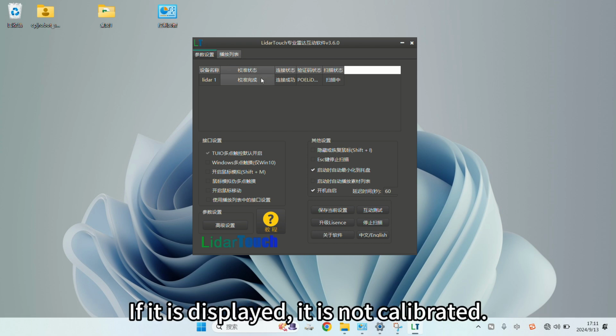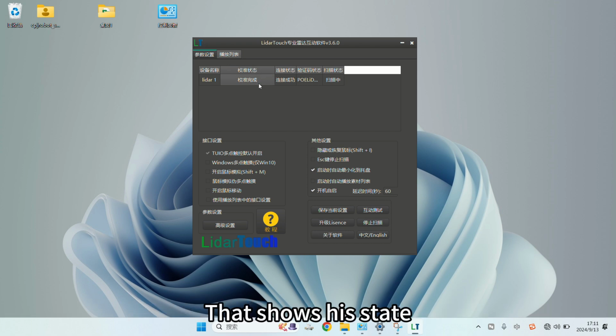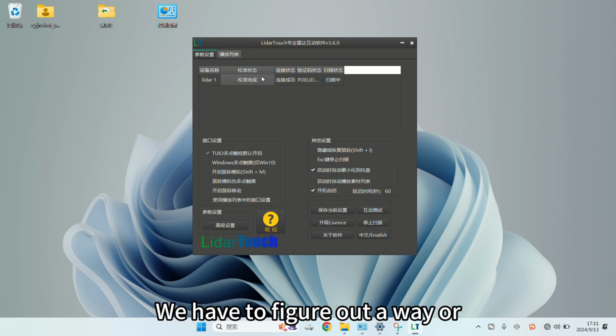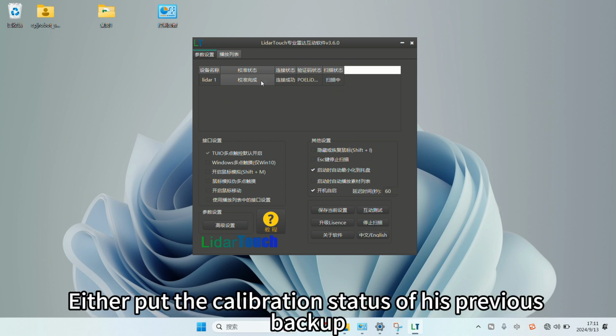Calibration status: if it's displayed, it is not calibrated. That shows his state - calibration status is lost. We have to figure out a way, either recalibrate it or restore the calibration status from a previous backup.